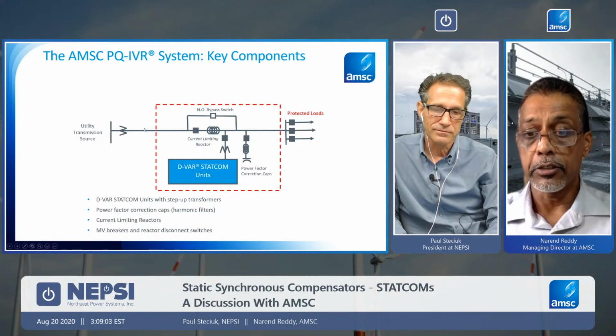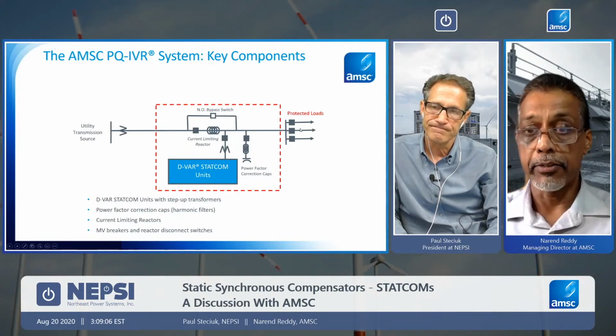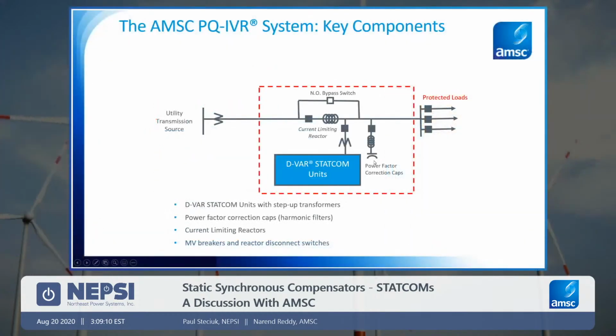So in essence, the PQIVR system main components, as you can see, are a utility transmission system, stepping down voltage to the local distribution. On the right-hand side, you have the protected loads. In the middle is an outline of the key components being used. As I mentioned, in some cases we would use a series reactor to adjust the short circuit capacity a little bit and make the system more effective. We have the STATCOM units that are really the heart of what provides voltage rebuild. And of course, some power factor correction cap banks. These are required, especially if we are using series reactors here to impact the fault power. These power factor correction cap banks become very necessary.